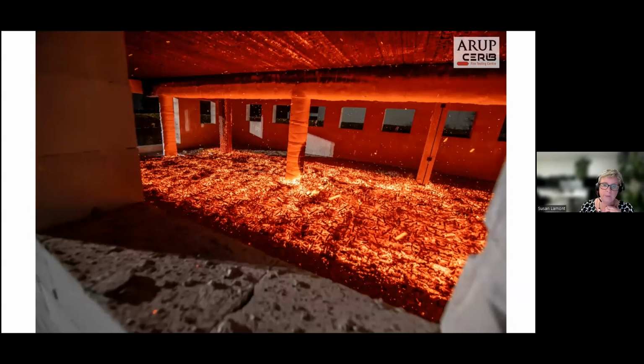Once the fuel and cribs on the floor had been consumed and only glowing embers remained, as you can see here, the flaming combustion on the surface of the CLT panels also reduced through small pockets. Those pockets continued to smolder for a significant number of hours - we had smoldering in the CLT ceiling and a lot of smoldering around the base of the glulam columns.